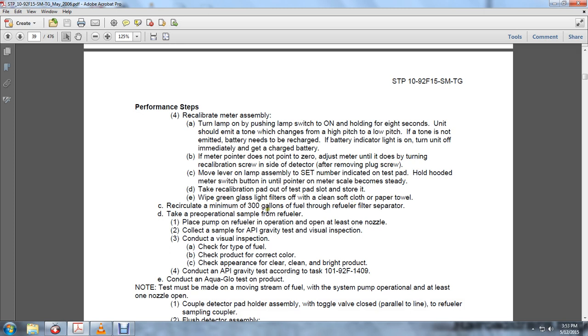Recirculate a minimum of 300 gallons of fuel through the refueler with a filter separator. Take a pre-operational sample from the refueler. Place the pump in refueler operation. Open at least one nozzle. Collect the sample. Conduct the API gravity test and visual inspection. Check the type of the fuel. Check the product for correct color. Check the appearance for clear, clean, bright product.